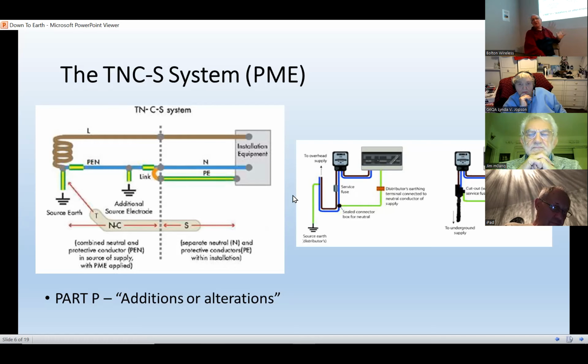Or maybe you have a metal tower in your back garden. You earth that, and you decide for safety's sake you'll connect that and bond it to your electrical installation as well. Normally there won't be a problem, but if there's ever a fault on the supply, and that earth connection on the neutral link disappears, where's the earth going to go?